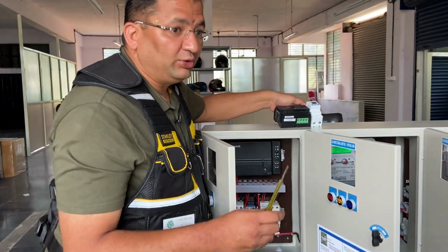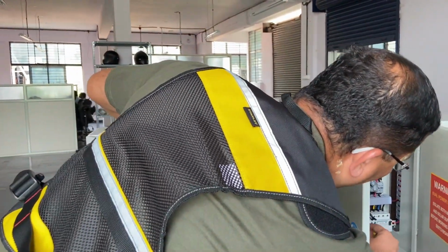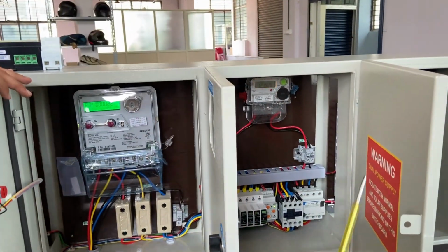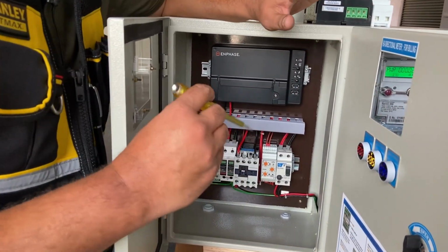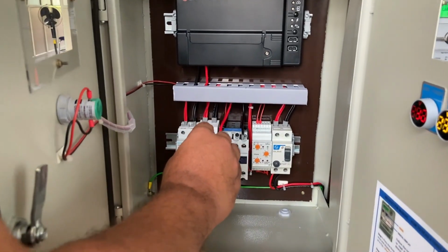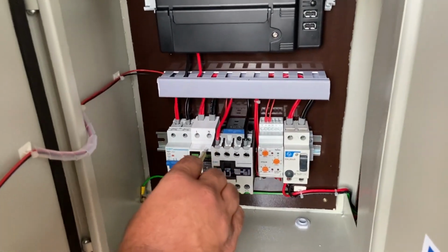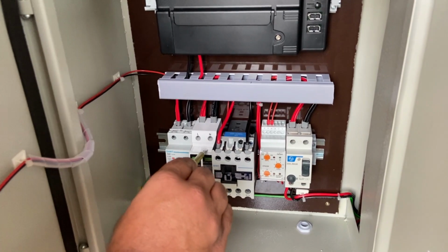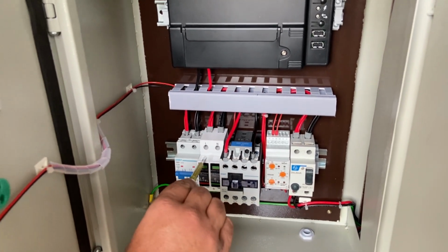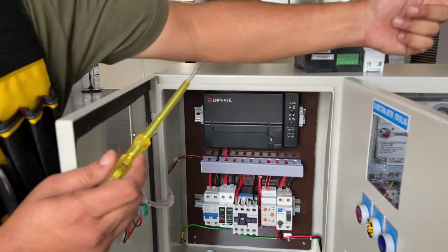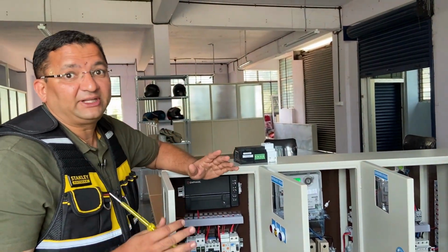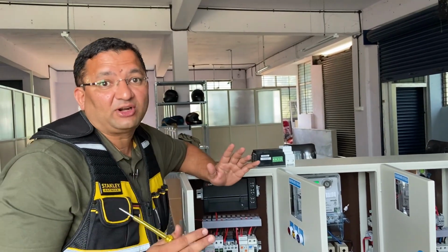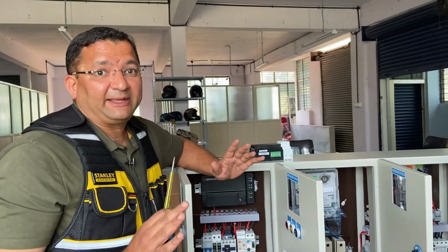And as I told you, type 1 SPDs or type 1+2 SPDs we install at the utility center, and the type 2 SPDs is at the load point. So this is not installed at the utility, this is not installed at the incoming. This is installed at the solar inverter side. So this is a type 2 SPD. However, type 1+2 or type 1 is at the utility center. So one must be careful that if we have a lightning arrestor installed at the site, it's very important to have a type 1+2 SPD at the utility center.